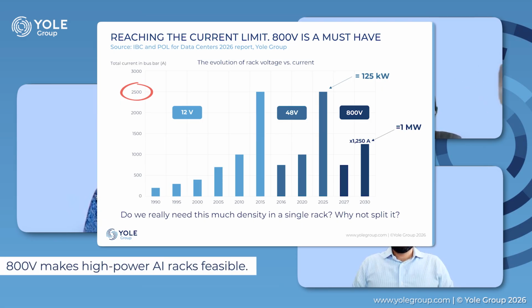Instead of putting several racks together to do this 1 megawatt rack, we do need this 800 volt. Why? Because if you divide the power by the voltage with a conventional 50 volt DC bus, you will get 20,000 amps in the DC bus bar if you divide 1 megawatt by 50 volt. So that's for sure unfeasible. It's physically impossible to have 20,000 amps in a DC bus bar. Copper will be, I don't know how many tons. So that's why we do need 800 volts. When we divide the 1 megawatt power by 800 volt, we reach 1,250 amps. So this is the reason why we do need 800 volt DC bus distribution.